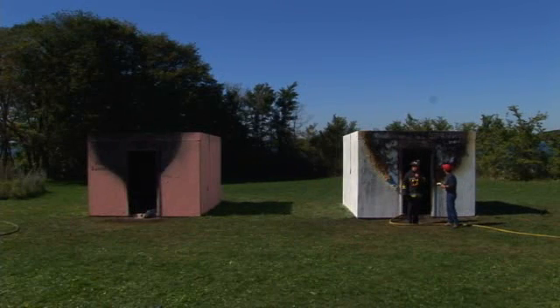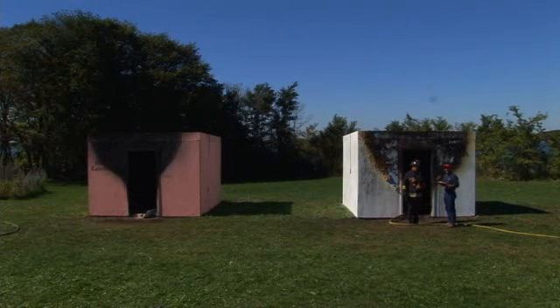You can see that the fire that sat in the corner in the room on the right — it didn't breach into the wall. The wall stayed intact. You could see the intumescent paint working: it bubbled up and kept the heat from transferring to the combustible wood inside the wall. By doing that, whatever was burning just sat there.